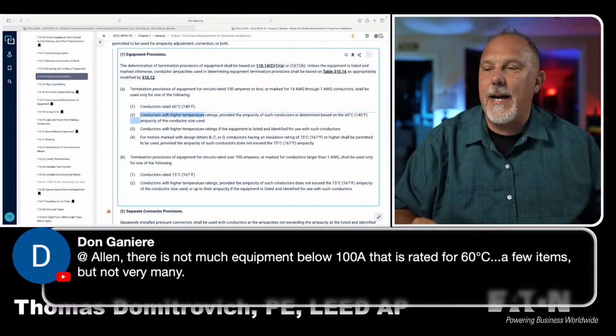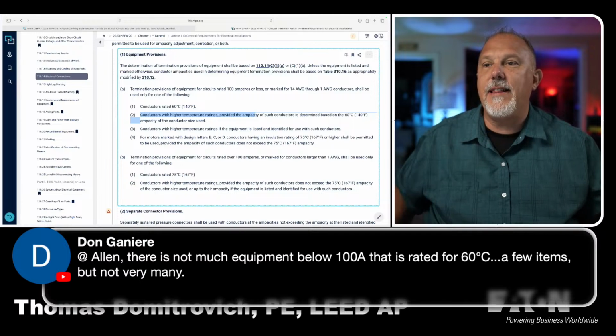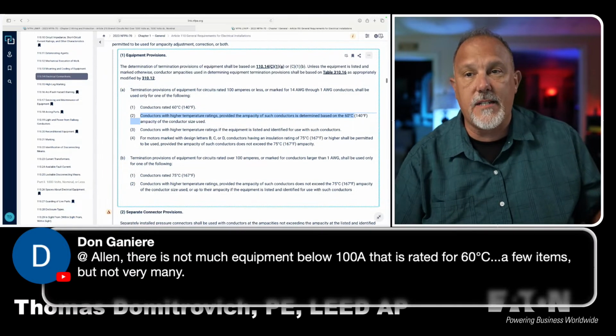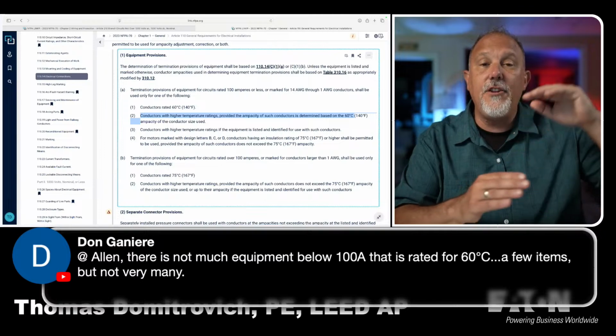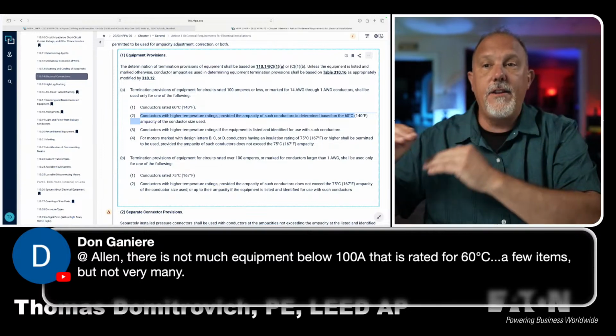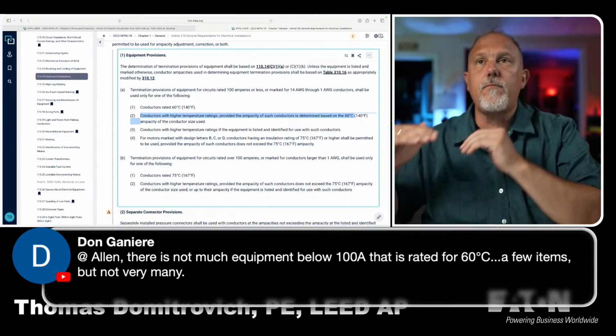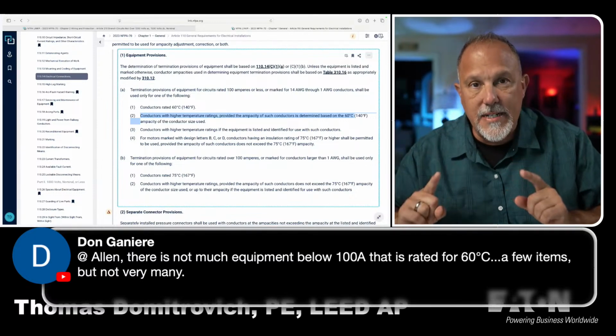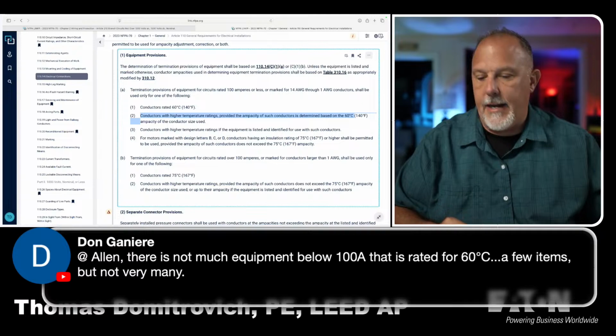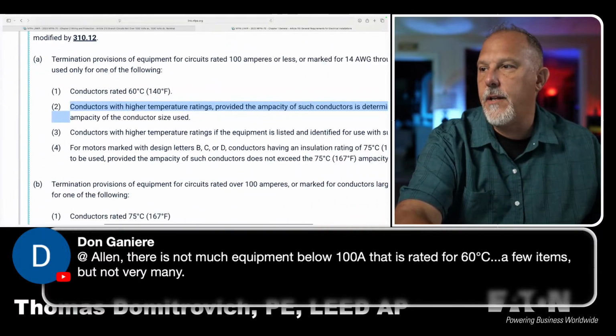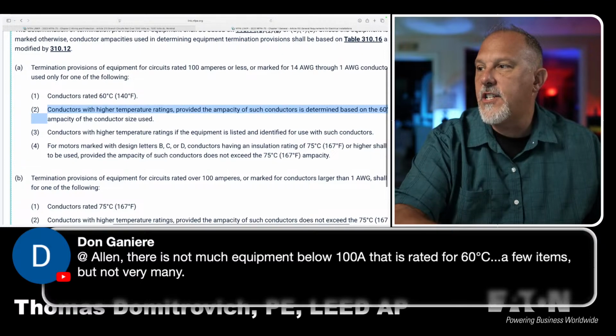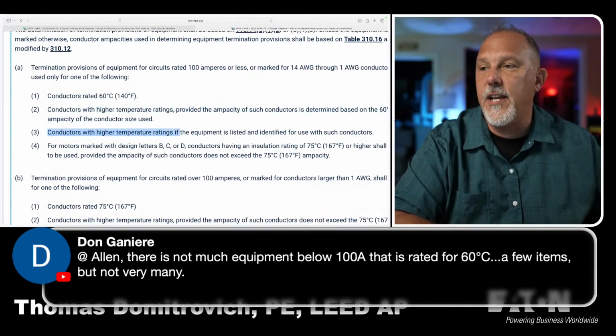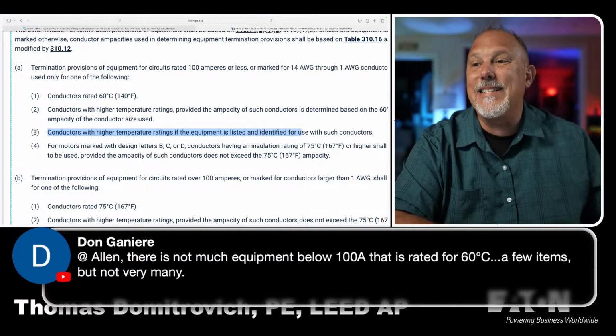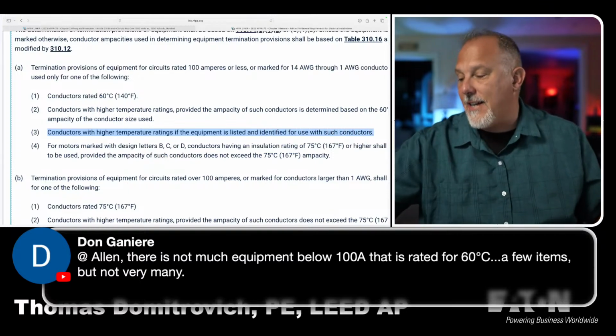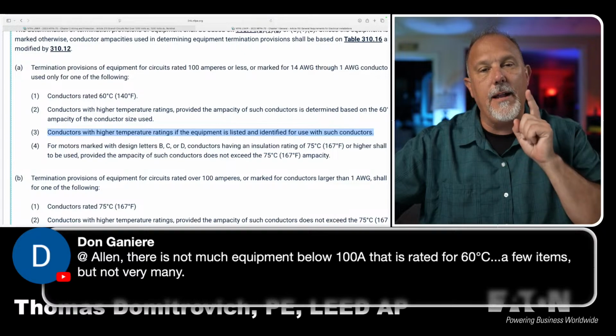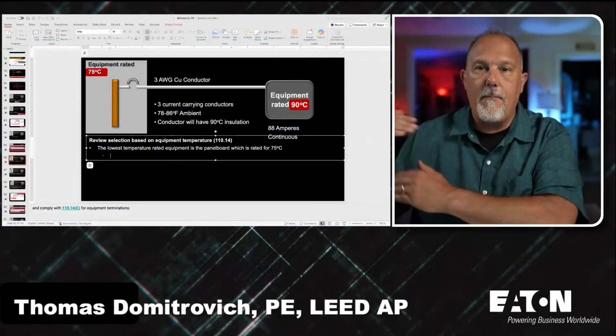Then it says conductors with a higher temperature rating, provided the ampacity of the conductors is determined based upon 60 degrees C. That's telling you that I could use a 90 degrees C conductor in 60 degrees C rated equipment, but I have to use a 60 degrees C column. This third item, let me zoom in a little bit. This third item, conductors with higher temperature ratings, if the equipment is listed and identified for such conductors, that's the one, Alan, that I am falling back on.